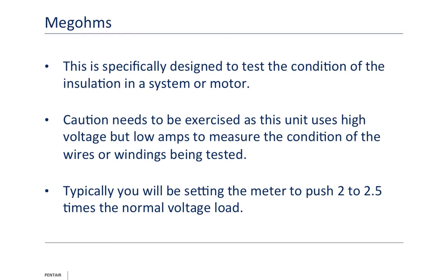In fact, especially for motors, it's not uncommon to leave that test go for 1 minute or 10 minutes, especially for maintenance measurements. So you're overcharging the unit specifically to see if voltage can leak. We're pressure testing the insulation, okay? You want big numbers: 20 million, 5 million, 2 million.